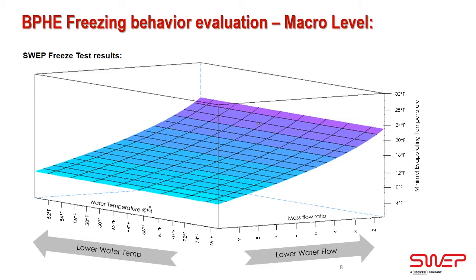under any possible condition. Also, this three-dimensional graph gives you an indication of the effect if you lower the water temperature. For example, you can see the minimal evaporating temperature is higher for a low water temperature than for a high water temperature. You can also see the effect if you lower the water flow for a constant refrigerant flow. And one additional comment, which I think is quite interesting: normally when I'm discussing with people what their expectations are in terms of minimal evaporating temperature, their expectation is much higher than what you can see on this graph. For example, on this graph you can see a minimal evaporating temperature of about 10 to 23 degrees Fahrenheit, which is quite low.